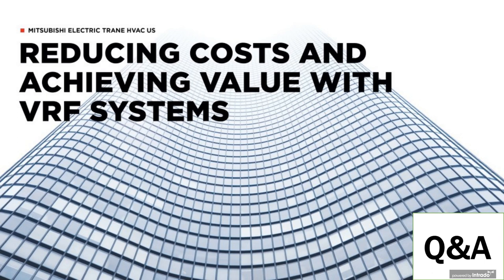Thank you. Another viewer asked, what are the primary differences between the various VRF systems? I think at their basic, a lot of the systems share some commonalities. The technology was born out of Japan and is really innovated from there on some pretty simple concepts. I would say the biggest difference that you're going to see is, and Jose briefly mentioned it, and I'll ask him to talk about it in more detail, 2-pipe versus 3-pipe. And when we say that, we refer to refrigerant piping, a liquid line, a gas line that go from the outdoor unit to the indoor unit.